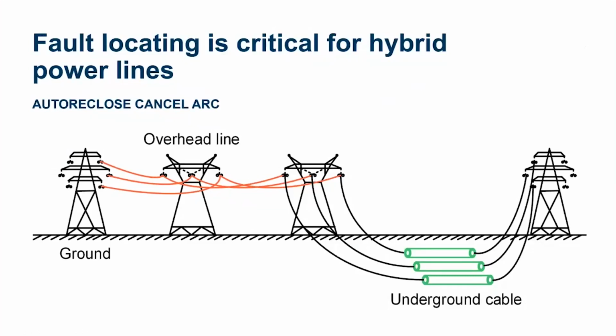The last section here that's cool is we can also apply this for hybrid lines. Let's say you have this line and you want to reclose for the overhead sections of the line, but for a fault that's on an underground cable, you can be pretty sure that it's going to be a permanent fault, and you don't want to be reclosing on a fault on this underground cable, further damaging the cable. So we can also create a section here for the underground cable to say I don't want to reclose if I detect a fault in the underground section.